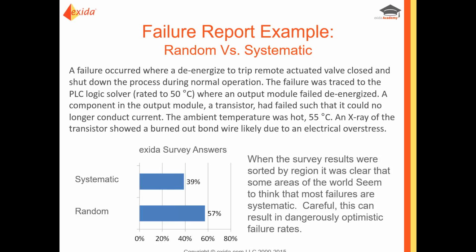And I will tell you that when the survey results were sorted by region, it was very clear that some areas of the world seem to think that most failures are systematic, and the failure reports are just thrown away, and you can imagine exactly what happens. The resulting failure rate calculation is extremely low, which can result in dangerously optimistic numbers to be used for probabilistic analysis.